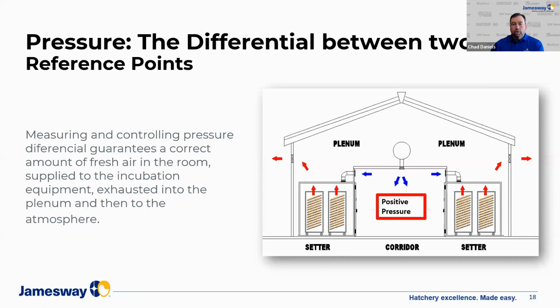And as we discussed before, with various types of incubation equipment, if this room is too cold, these machines will try to restrict how much air comes in. If it's too humid or lacks humidity, again, it's going to change the volume that it consumes. So controlling this pressure to an accurate point, that's the first key piece of making sure that we're providing enough air into the room. The second piece of this is, where's my reference point? So under normal circumstances, when we talk about rooms, we generally reference a room to an atmosphere. And so when we say a room is slightly positive, we should be saying it's positive in reference to atmosphere, or to where its reference point is. So under normal circumstances, this should be your two references for the room.